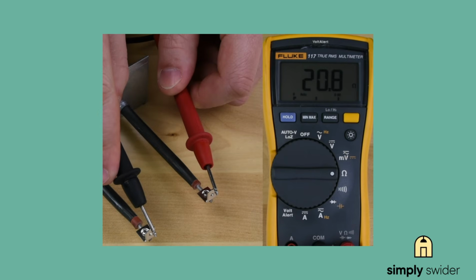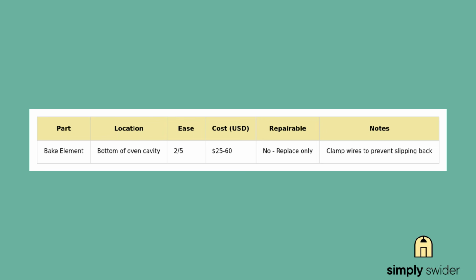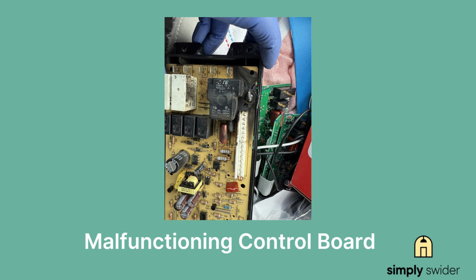A good element should read between 19 and 29 ohms. The fix is pretty straightforward. First, turn off the circuit breaker and unplug the oven. Never skip this safety step. Then remove those mounting screws, pull the element forward, and disconnect the 2 wires. Pro tip, use a clamp or put a kink in those wires so they don't slip back into the wall on you.